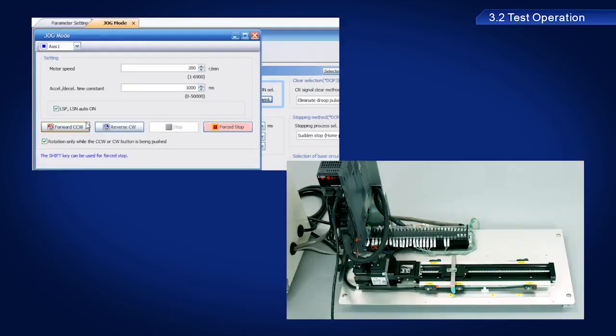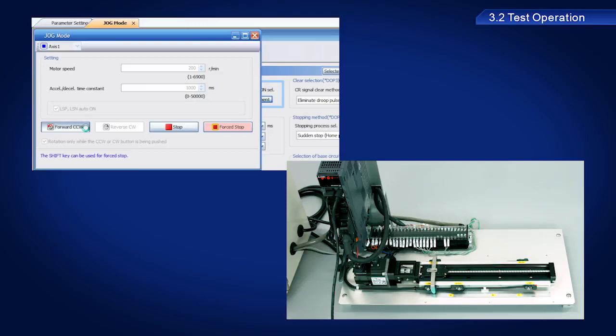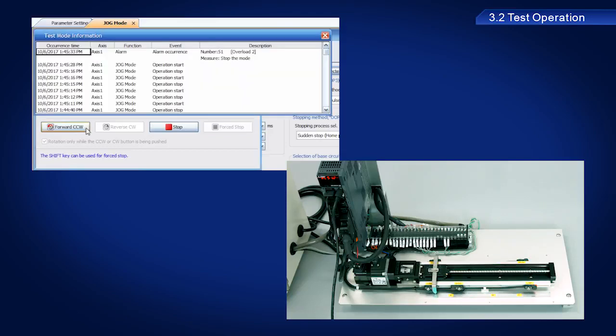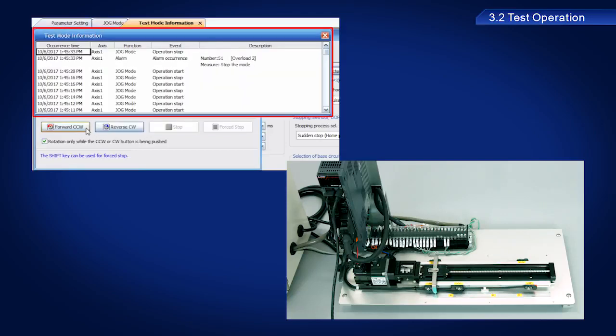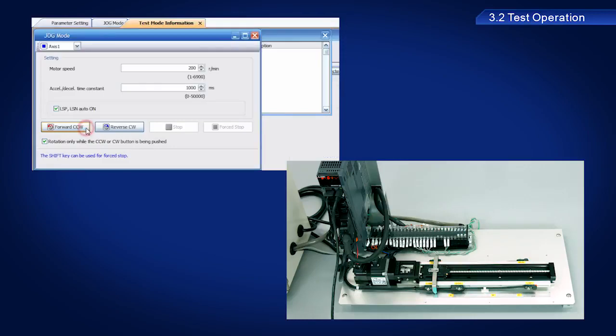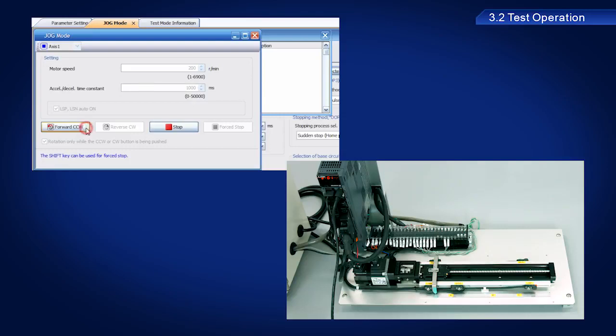If the LSP or LSN limit is exceeded during this time, the servo amplifier will stop and an alarm display appears. Once the servo amplifier stops, clicking the forward CCW and reverse CW buttons will have no effect.